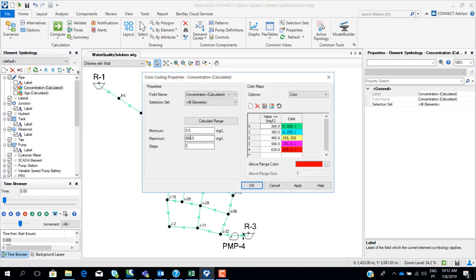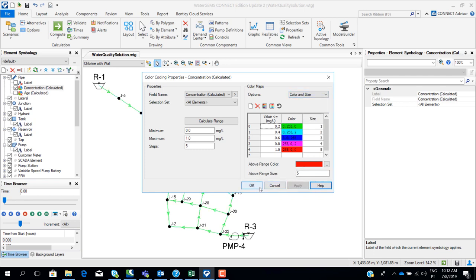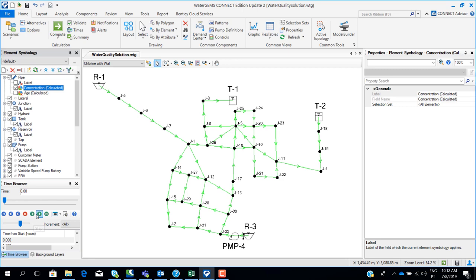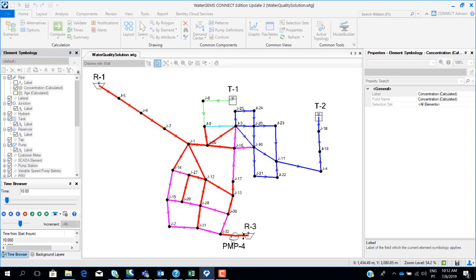I just need to change these values because this field concentration is used to simulate any constituent. In the previous run we were simulating total dissolved solids which have different concentrations than chlorine — chlorine is typically at much lower concentrations. So I redefine the range: red for bigger concentration, green for lower concentration. Now we can see that the sources of chlorine are the reservoirs — reservoir one and reservoir three — where we have higher concentrations.